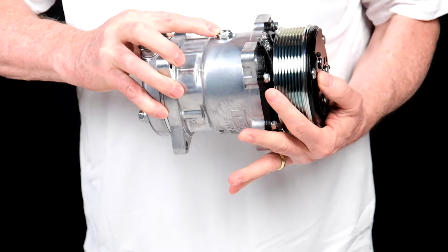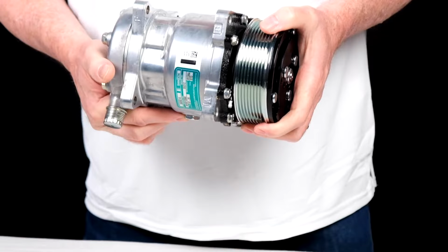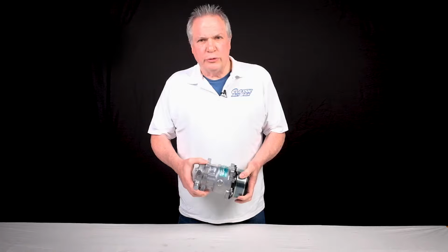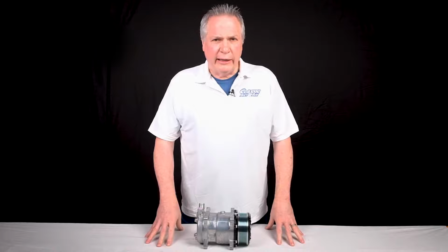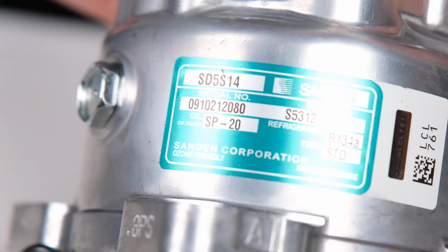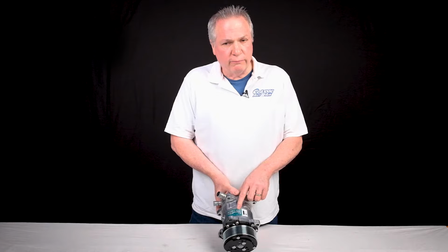If you have a question about how much oil is in your compressor, you'll need to remove the drain plug and turn it upside down on a collection device for at least 8 to 10 hours. Once you drain the oil out of the compressor, you'll need to flush the rest of the system to remove all the other oil. And I would recommend replacing the dryer, because the dryer stores a fair amount of oil. That way you can go back to the tag and it'll tell you how much oil was in the system, and that's the oil charge for the whole complete system.